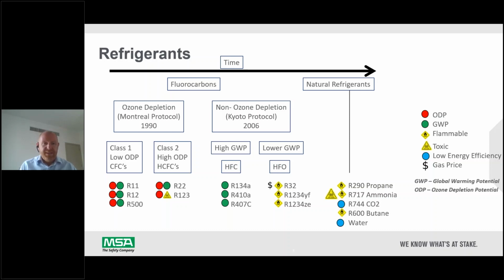So HCFCs were invented so that they reduced the chlorine atom and brought in a hydrogen atom in order to reduce the ozone depletion potential of these gases. That was the likes of R22, R123. Then global warming became a huge concern globally, and some of the damaging gases were refrigerants.